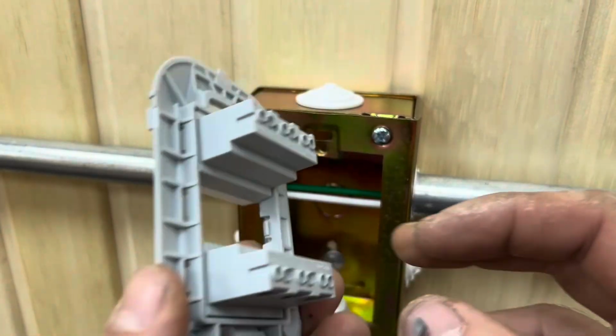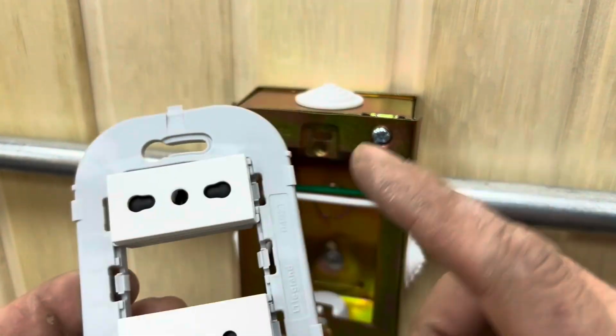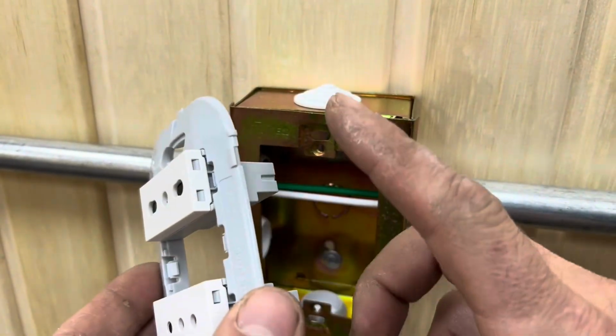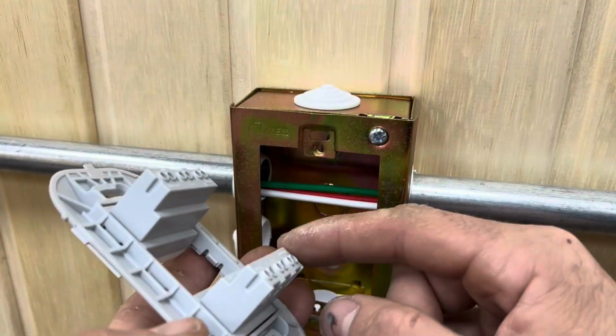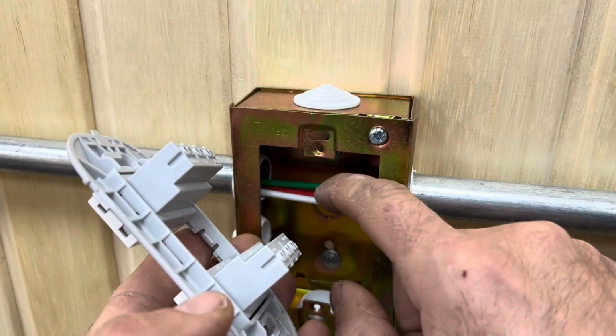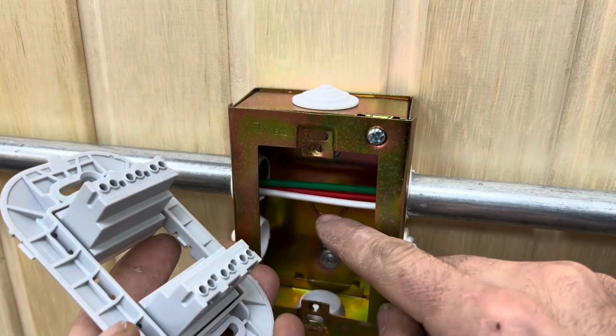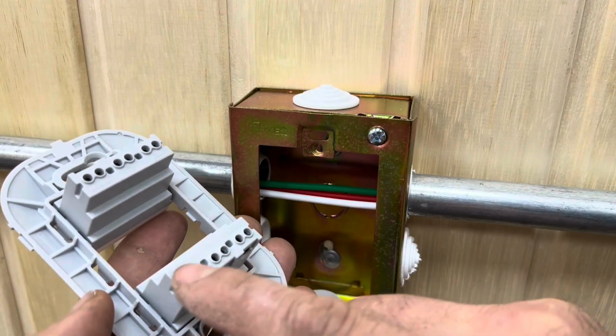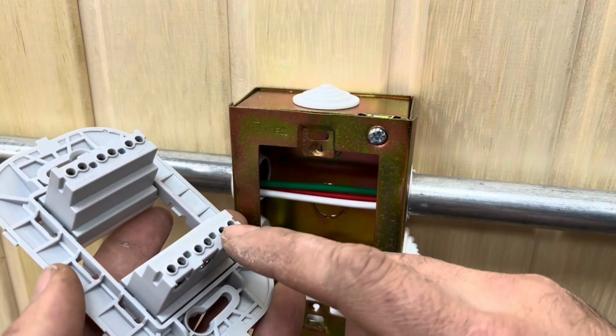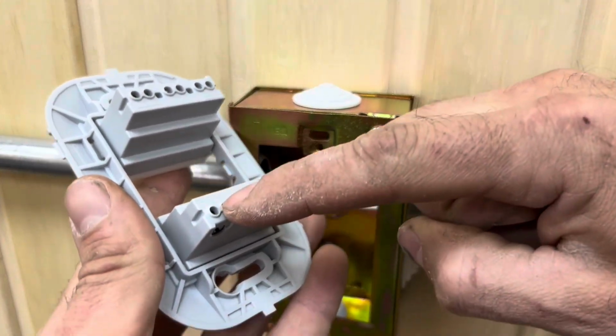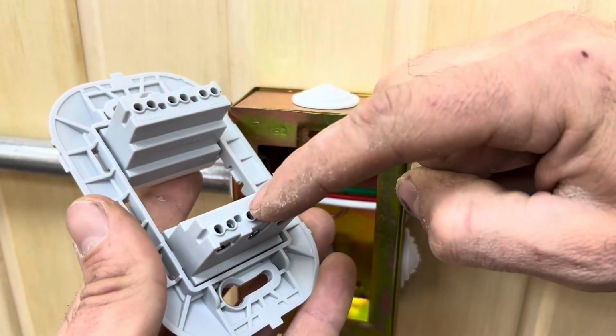To connect this double outlet, we're not going to use a jumper. We're going to connect them in parallel. What does it mean to use a jumper? Basically, it's connecting each of these wires to one of these holes, phase, ground, and neutral, and then using a short wire to make a bridge over there.